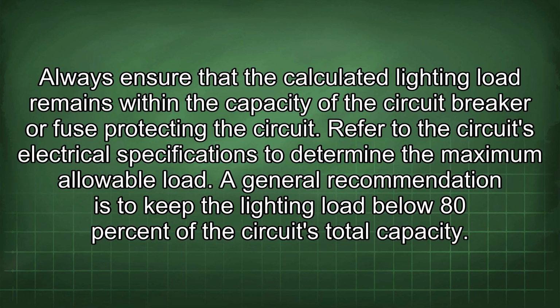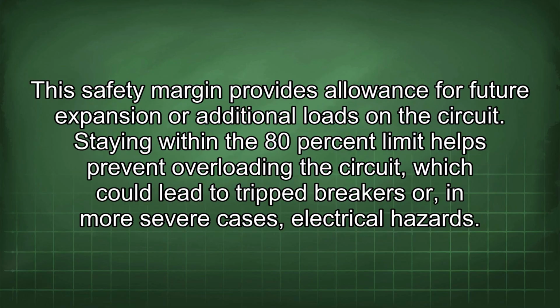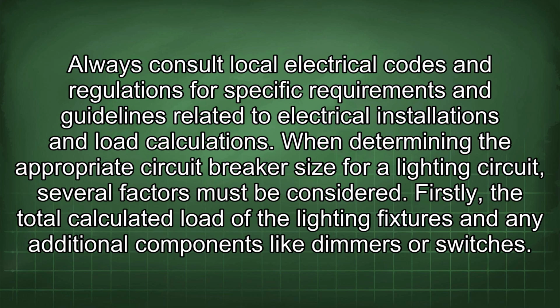A general recommendation is to keep the lighting load below 80% of the circuit's total capacity. This safety margin provides allowance for future expansion or additional loads on the circuit. Staying within the 80% limit helps prevent overloading the circuit, which could lead to tripped breakers or, in more severe cases, electrical hazards.